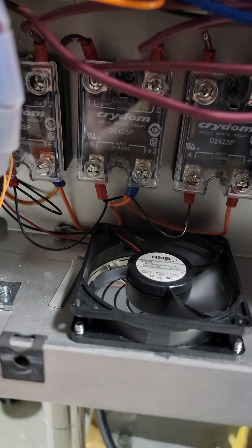Anyway, I've been having some issues with the heating, and I did some troubleshooting. I know it's not the SSR, it might be the contactor, it might be the heating element. I can't test the heating element because each heating element is crimped to the next one, and I don't want to cut these off. So I was hoping they'd tell me an easier way to do it. So that's not good.